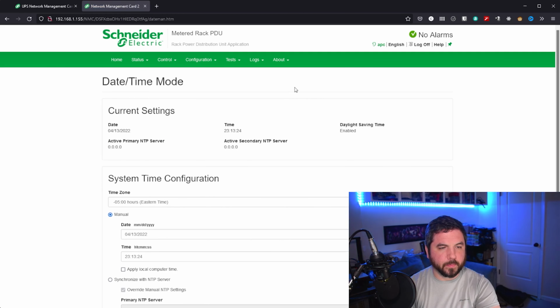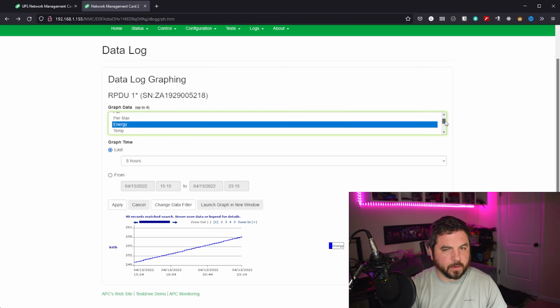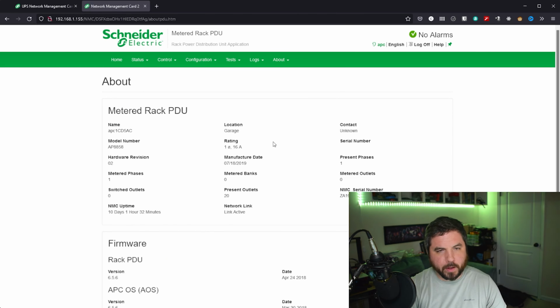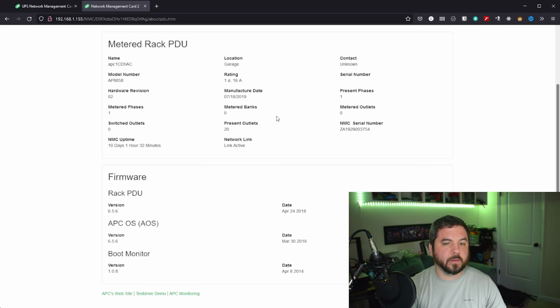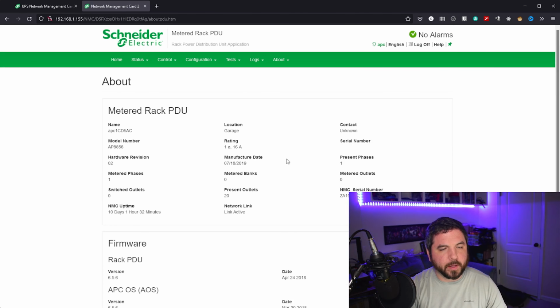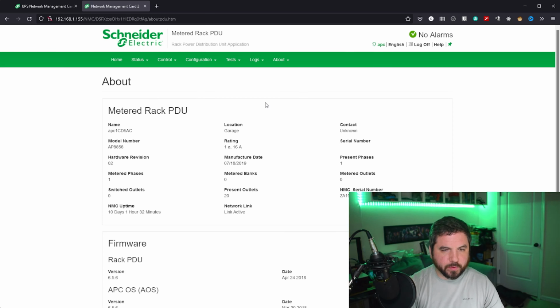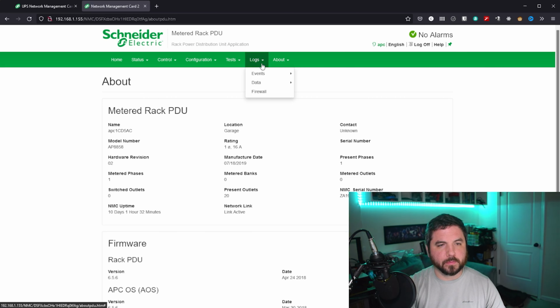One thing I didn't cover on the other unit is the date time mode. You can actually connect to an NTP server if you want to, or you can apply local computer time. As you can see, there's a lot available here. If you want to see the energy usage over time, it's pretty much a steady linear graph. And here's the About page. We have more of the model information, the revision, when it was manufactured. Firmware of the UPS and the firmware of this PDU are fairly similar, and they seem to be cross-flashable, so just be careful about that when you do updates. If you do manage to flash over one versus the other, you just need to FTP in and do a manual flash.